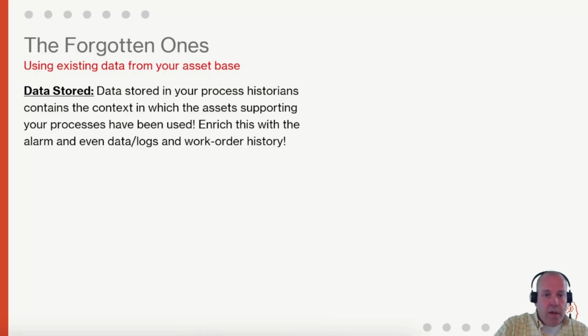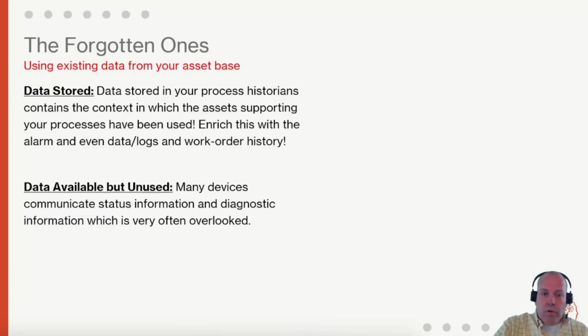You may not be able to detect and monitor all fault mechanisms of your assets, but it's very often a good start. In addition, you can tap into the data that is available but unused and often not unlocked. Most of your instruments and actuators are capable of communicating diagnostic information, which is often overlooked or only consulted during manual inspection rounds, for example.